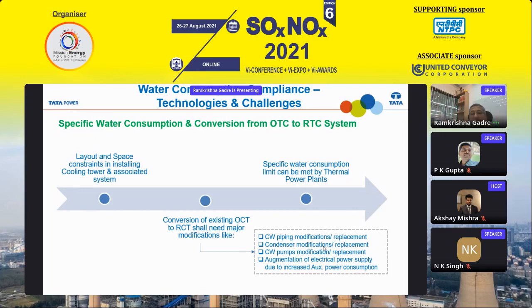Otherwise, the fume and water particles will affect the structure in other areas, and our interface will also be there. Even the auxiliary power consumption will go up, and the whole CW system may change. Even the condenser might not be designed for that much pressure. So it may look like simply changing from once-through system to cooling tower, but there can be a good number of changes into the whole cooling system, including the condenser, pumps, and piping also.